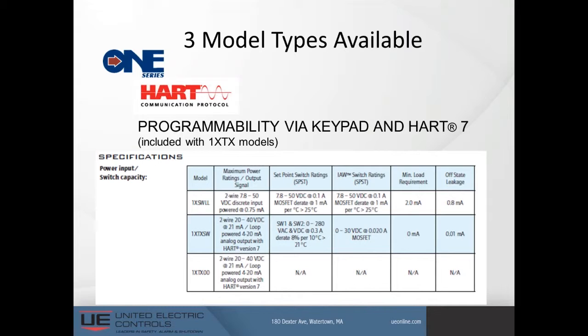But the cool thing is that this now is a HART version 7 capable device. What that means is that you can walk up to this with your Meriam HART calibrator, or there's a P&F computer-enabled calibrator that you could plug into the 1 Series, and it can now be programmed via HART, including the settings of these switches, the deadbands of the switches, including whether or not you want to use latching or non-latching relays, the plug port technology.